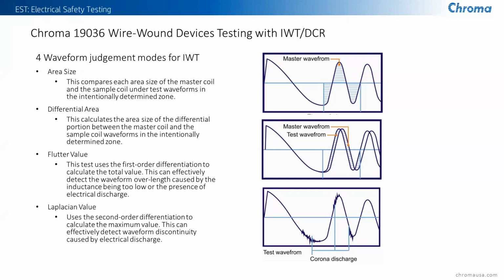Flutter value, this would be something that would be a possible anomaly related to a possible partial discharge that's occurring winding to winding or layer to layer. And with this flutter value, you might be able to detect a very fast, sudden change. And that change could only be detected with the high-speed sampling that we can do when we evaluate the waveform. The same type of test at a different level would be the Laplace test, which gives us the ability to do that and also detect such things as corona or partial discharge.